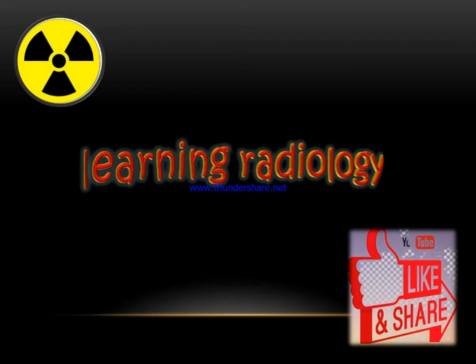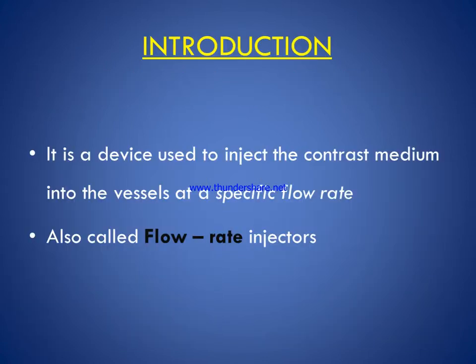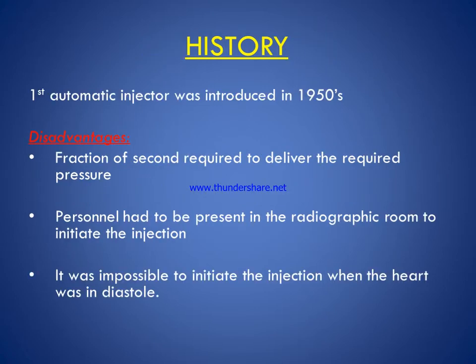Hello everyone, welcome to our YouTube channel Learning Radiology. Today's topic is the pressure injector. A pressure injector is an electromechanical device which is used to help deliver contrast medium into vessels at a specific flow rate. It is also called a flow rate injector.